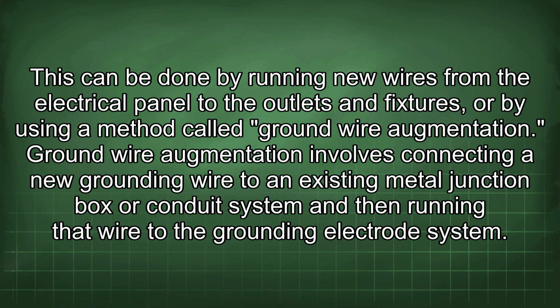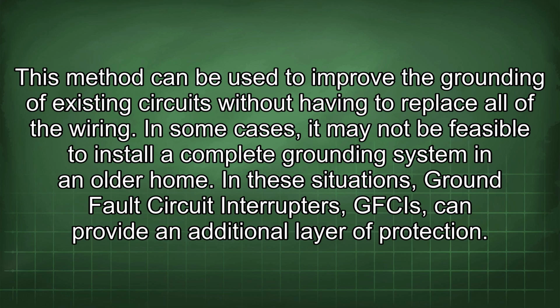Ground wire augmentation involves connecting a new grounding wire to an existing metal junction box or conduit system and then running that wire to the grounding electrode system. This method can be used to improve the grounding of existing circuits without having to replace all of the wiring.